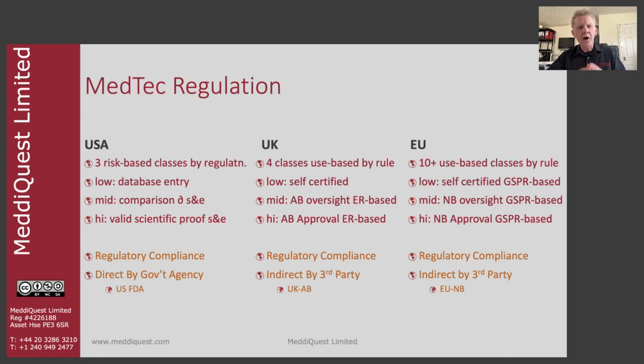So where are we? If you look along the first line, each one of these jurisdictions has a risk-based class system. In the US, we've got 3 classes by regulation. In the UK, 4 classes based on rules. In the EU, 10 plus classes now, based on rules. So what does this actually mean? Yes, the concept is the same. The implementation and the detail is very different in the different jurisdictions.